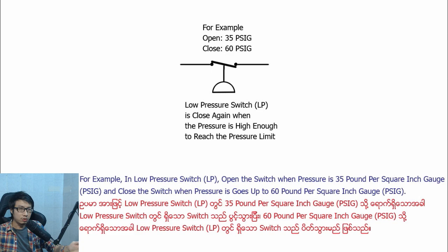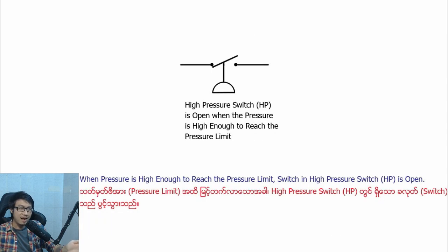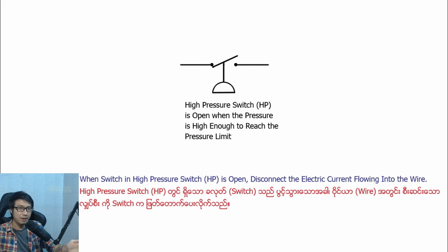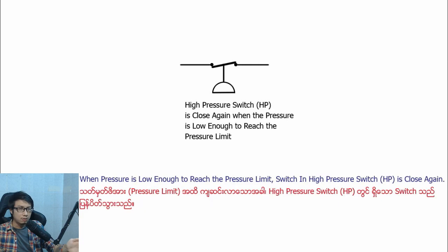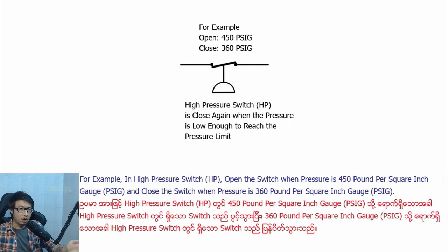For example, in the low-pressure switch, the switch opens when pressure is 35 PSIG and closes when pressure goes up to 60 PSIG. When pressure is high enough to reach the pressure limit, the high-pressure switch opens and disconnects the electric current flowing into the wire. When pressure drops low enough to reach the reset limit, the high-pressure switch closes again. For example, in the high-pressure switch, the switch opens when pressure is 450 PSIG and closes when pressure drops to 360 PSIG.